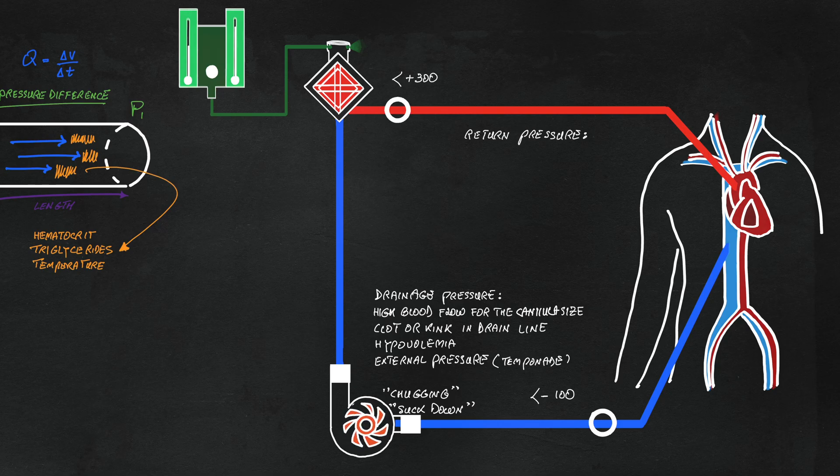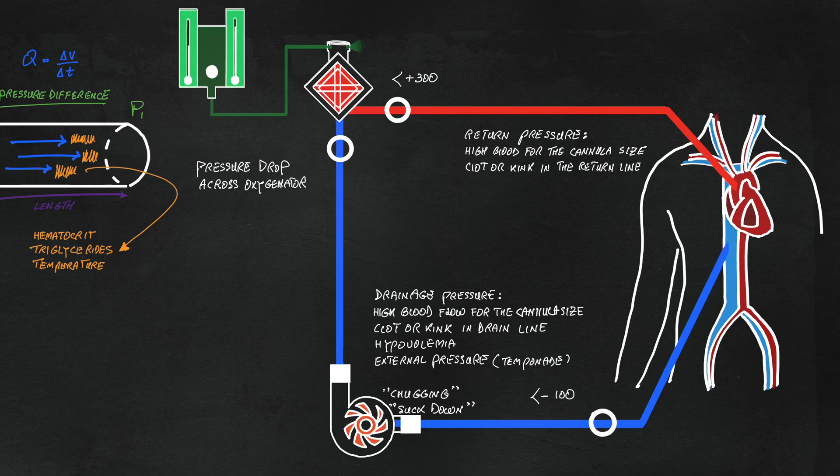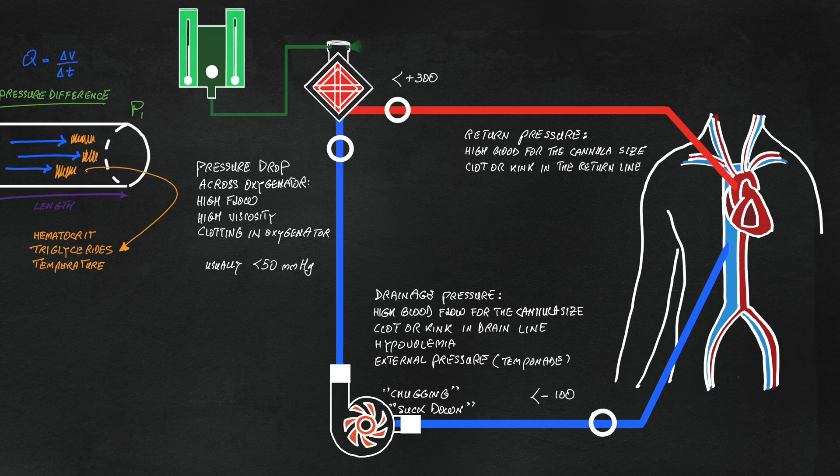Return pressure will be higher with high blood flow relative to the tube size, or if there is a kink or flow impediment. Another clinically important parameter is the pressure drop across the oxygenator, which could be due to high viscosity or clotting.